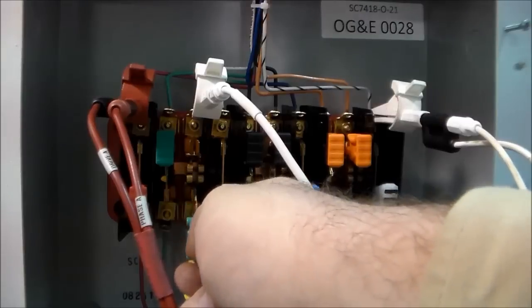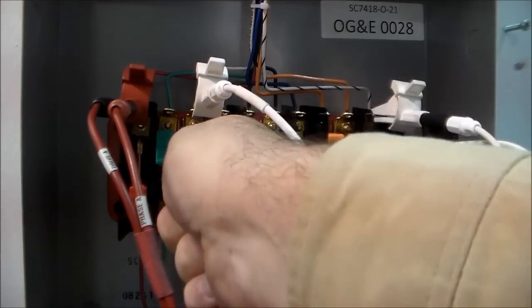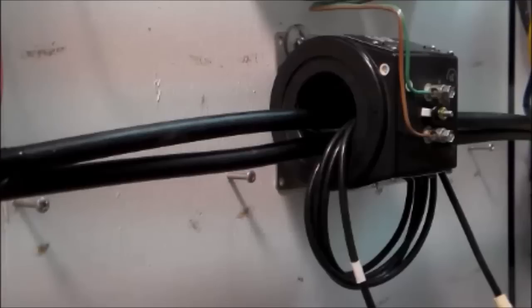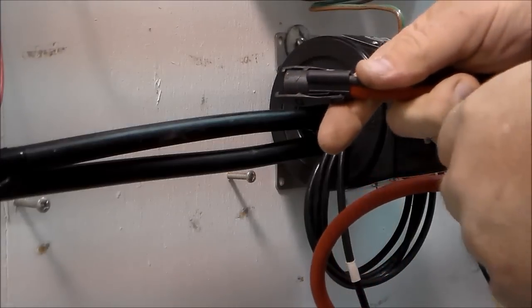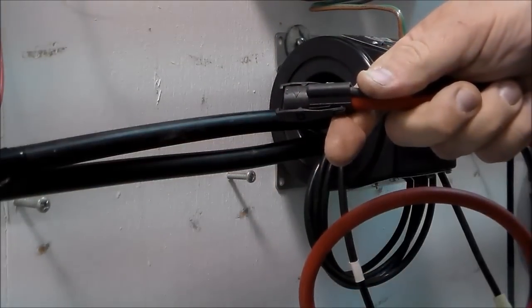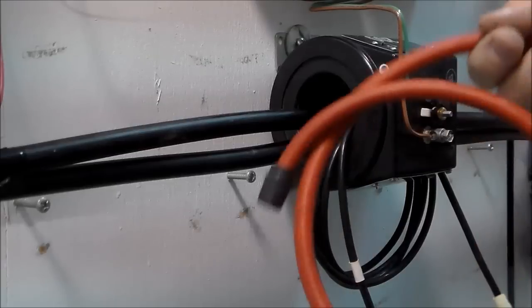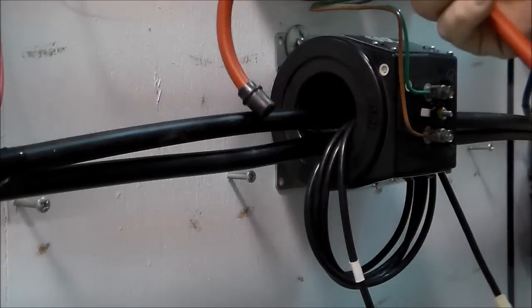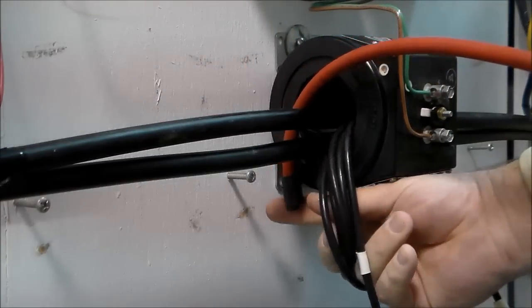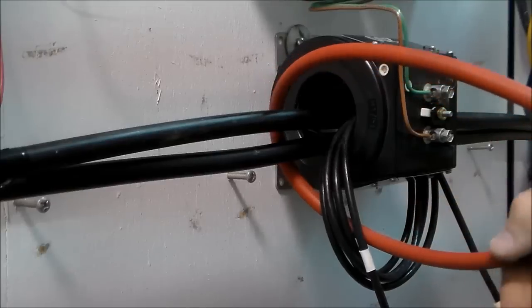To break the connection in the test switch, we'll insert an isolation stick. The drive cable is installed just as before, anywhere from 1 to about 5 turns. Depending on the conditions at your site, it may be safer just to use 1 turn. And the last lead we'll hook up is a flexible current probe. Check your current flow arrows on the probe and ensure that the probe goes around the customer's wire and the drive cable turns. And that's about it for cables and connections. Up next, the test set.